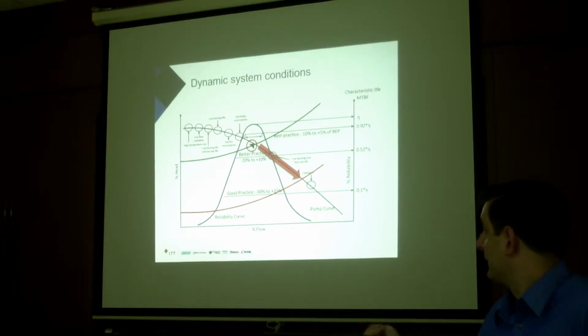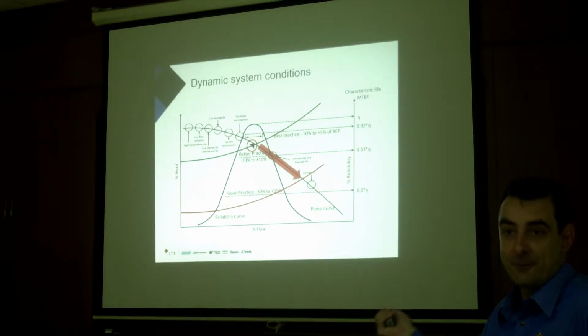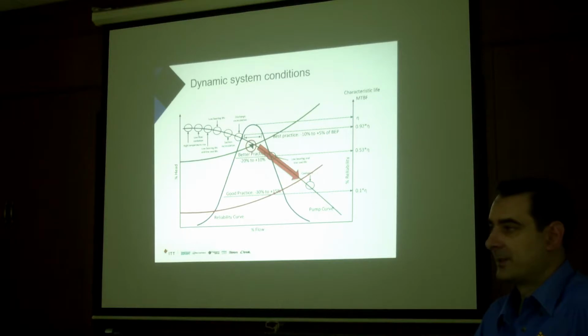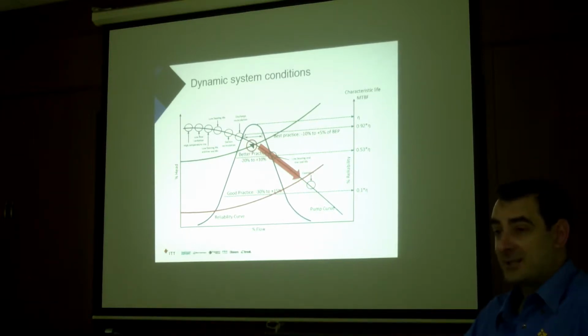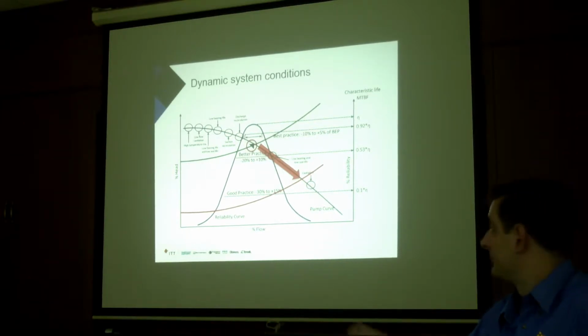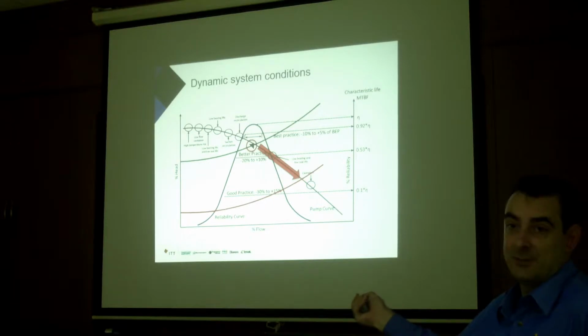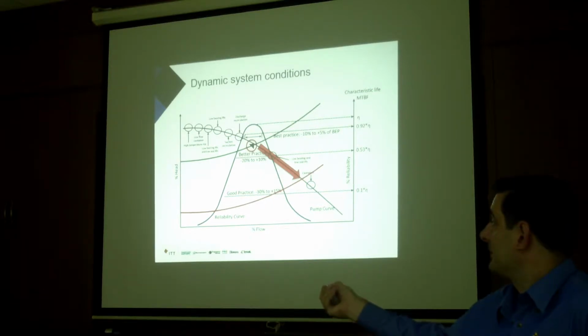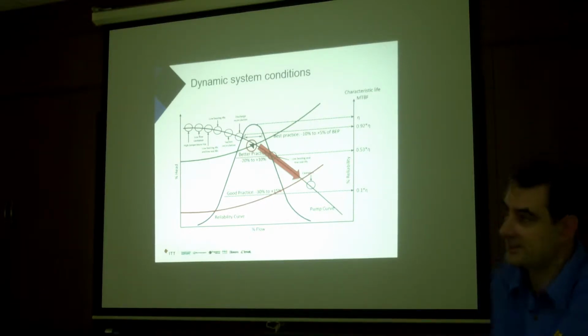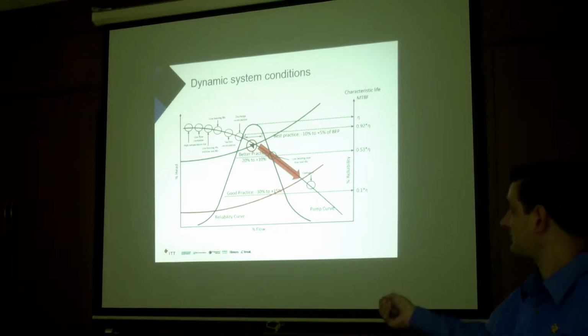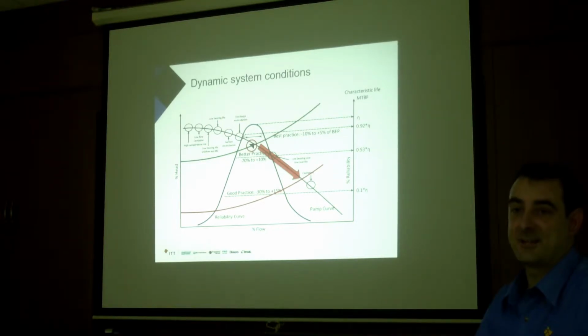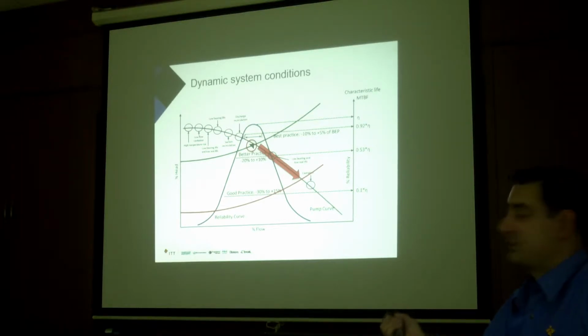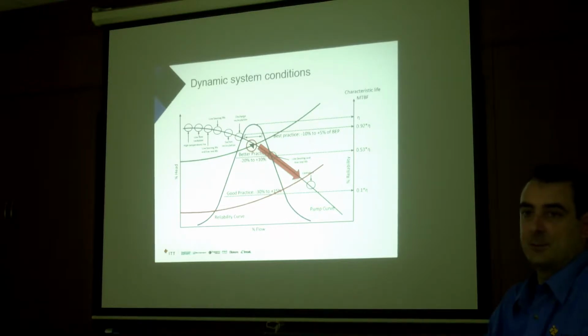At that point, you cannot push enough flow into the pump to satisfy the pump flow rate. It's just well beyond. Actually, that is more destructive. This can be more destructive in the long term than running here. Because running here, a lot of times the calculations are a bit conservative. You can probably run there longer than you say. As long as the liquid is cold, maybe it will be okay.